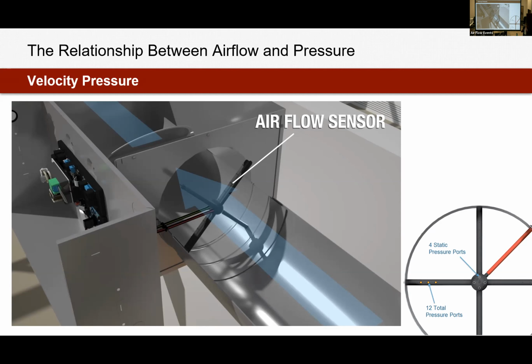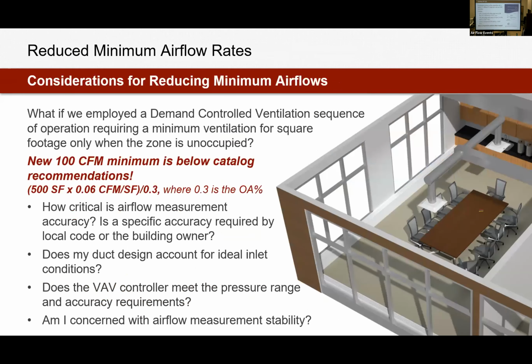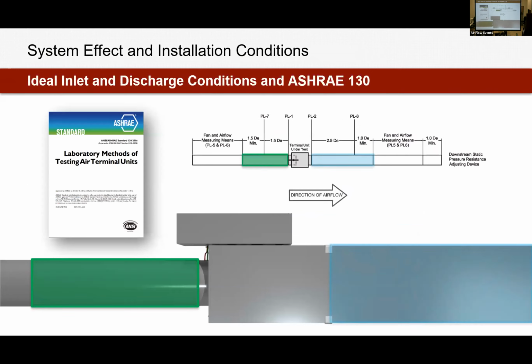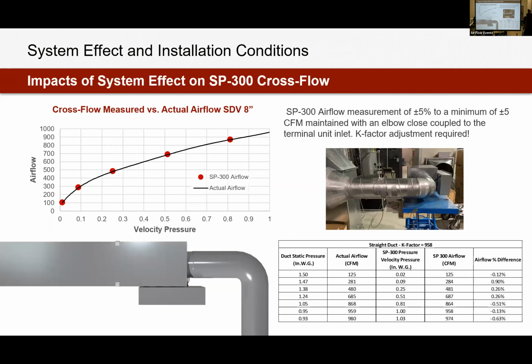If you have a linear flow ring, maybe one that's a diamond shape that doesn't have an averaging sensor in the middle, that's how you're going to result in poor readings or measurements because those pressures aren't actually measuring together. If you've got, pretend this is a linear, whatever port is up here is going to have a higher influence on the reading than maybe the one down in this corner. Because of that center averaging chamber, we were able to maintain the plus or minus 5%.